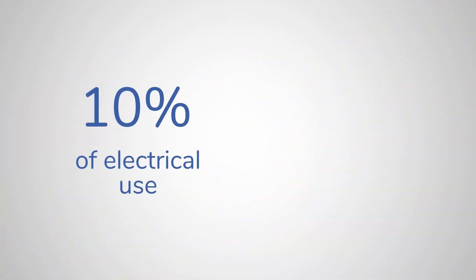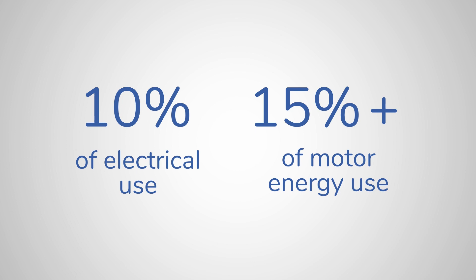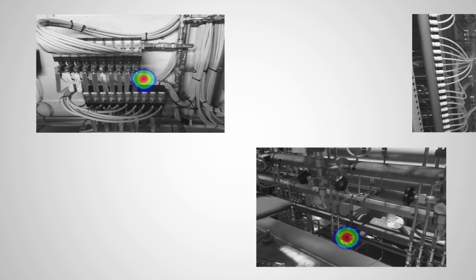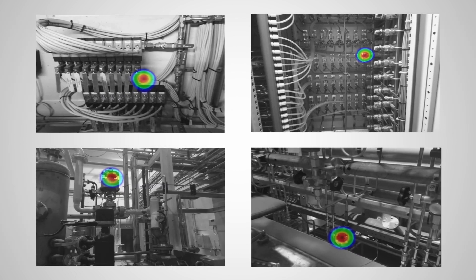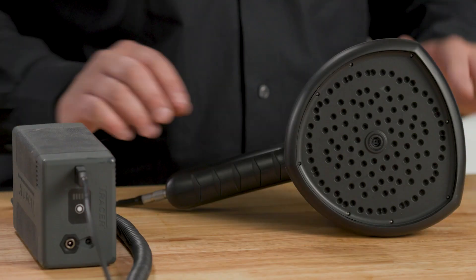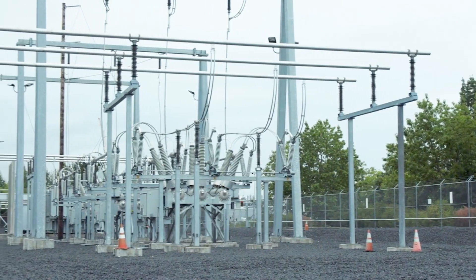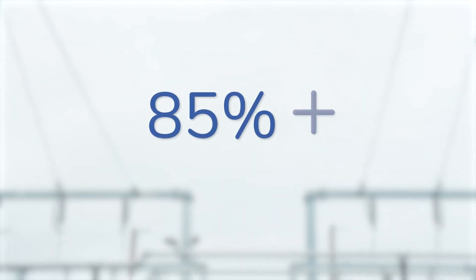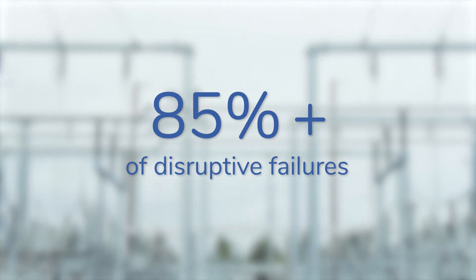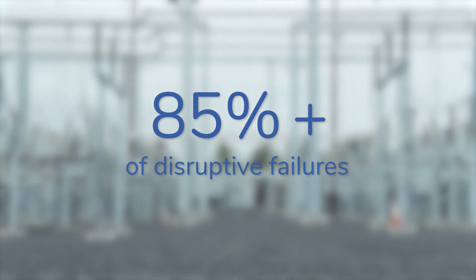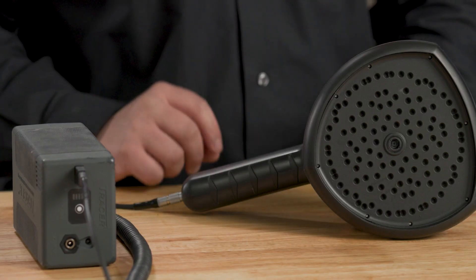As for return on investment, consider this: compressed air systems account for 10% of electrical and more than 15% of motor energy use by U.S. manufacturers. So when these systems leak, the resulting energy loss, safety hazards, and cost of replacing equipment make the SI124 critical to finding and repairing leaks. And as for electrical systems, more than 85% of disruptive failures in high and medium voltage equipment are related to partial discharge. The FLIR SI124's ability to accurately locate and assess partial discharge makes it a valuable inspection tool.